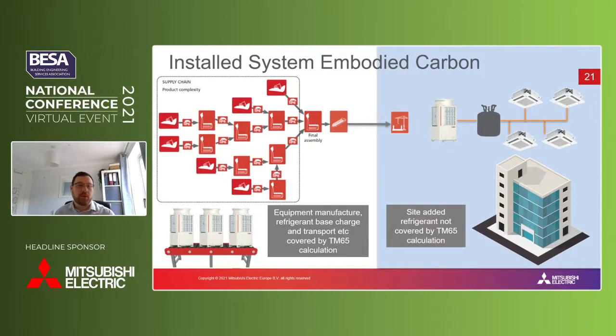And to conclude, products are obviously not used solely in a building. Components are often brought together to provide a solution for heating, cooling, and ventilation. When it comes to direct expansion products such as split systems or VRF systems, there is usually additional refrigerant added on-site to allow for extended pipework separation.